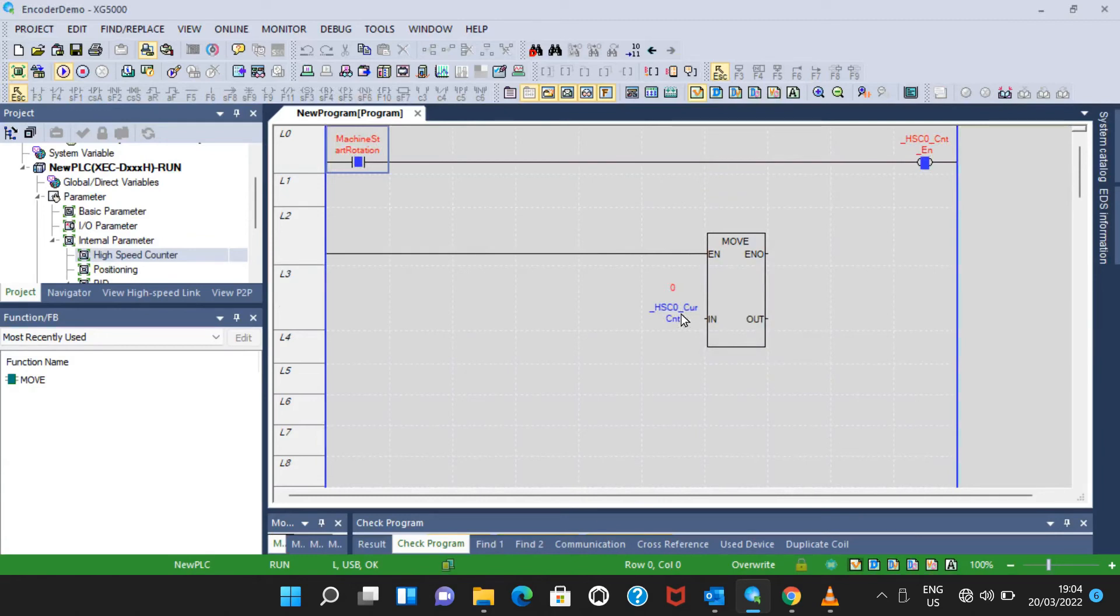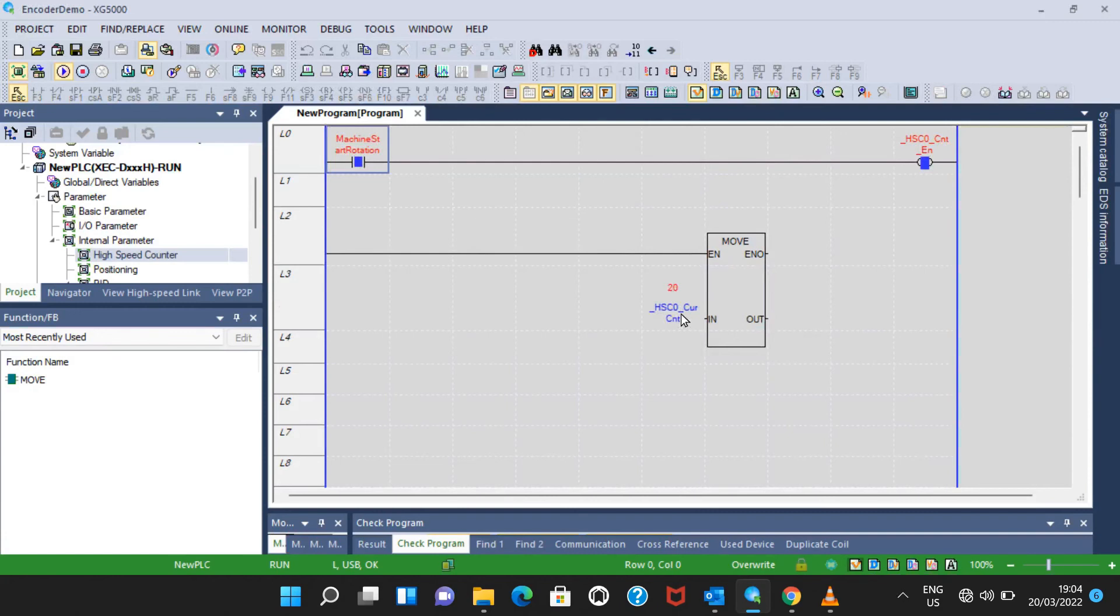Now if I'm rotating in one direction it is showing me negative, and if I'm rotating the opposite direction it is showing me positive. So that's how we can monitor the encoder on PLC.